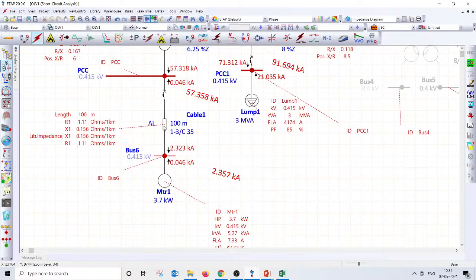And imagine if it is a 4 square cable or a 6 square cable, what would the current be? That current could be a few amps, not really in kiloamps. And if the length increases, the current will further come down. That's another note which you need to note.